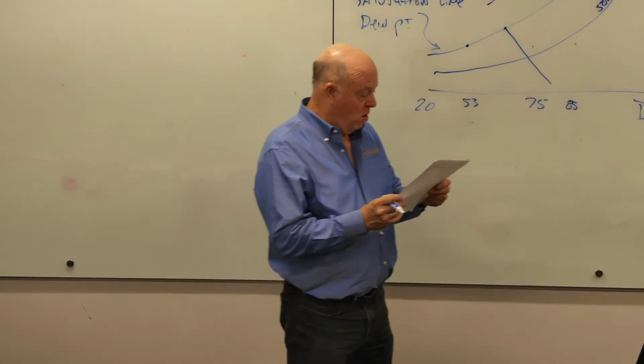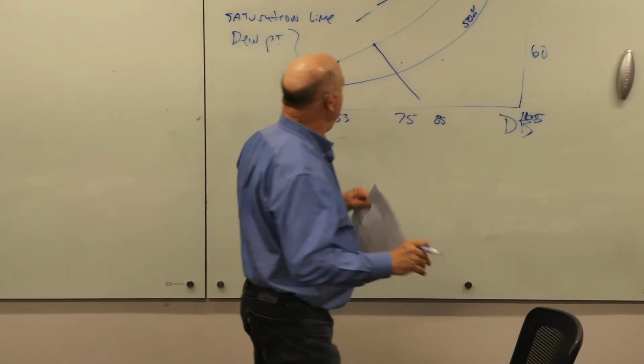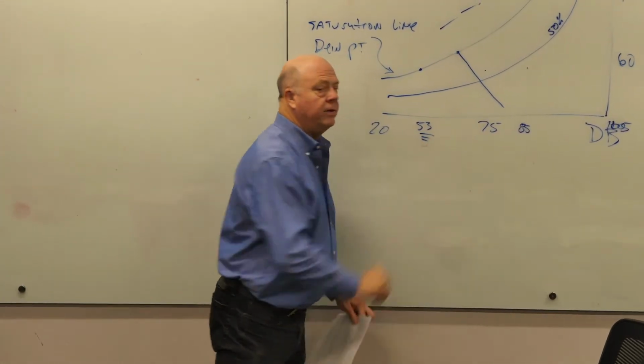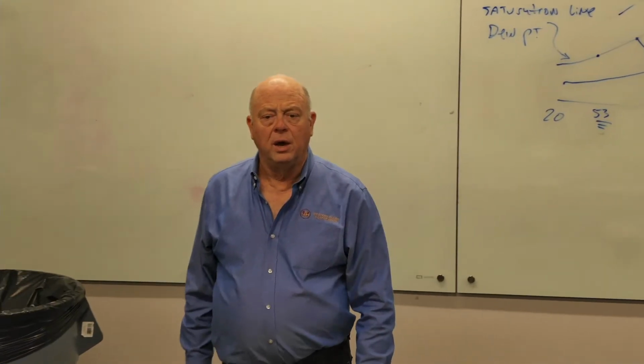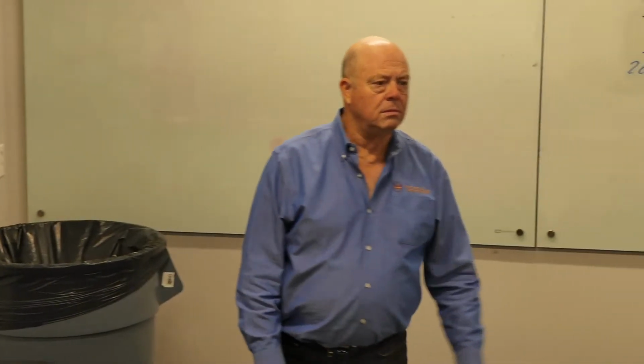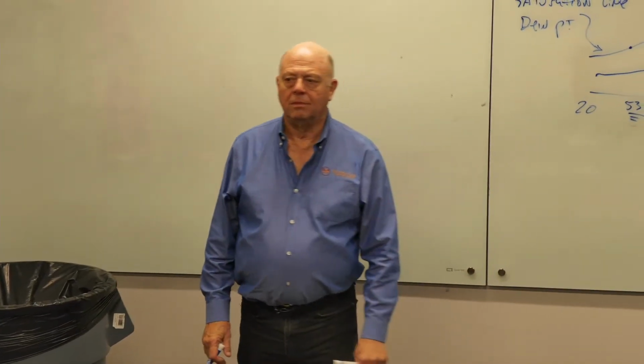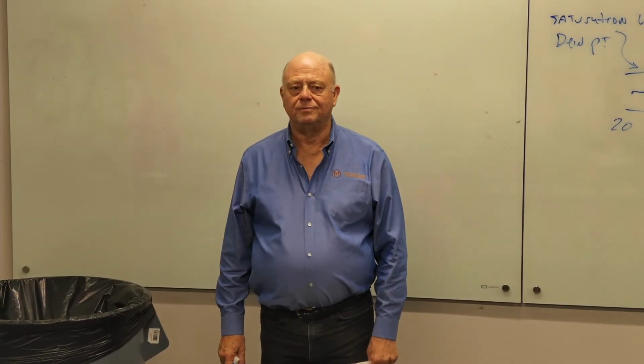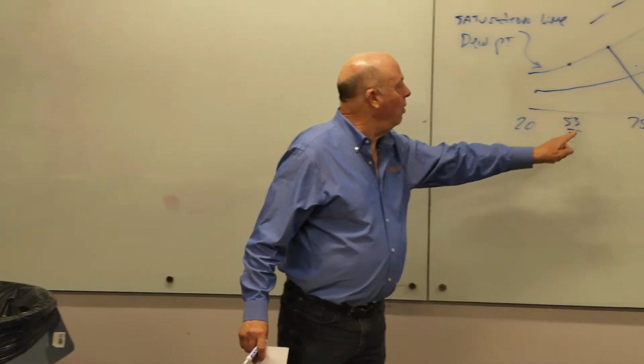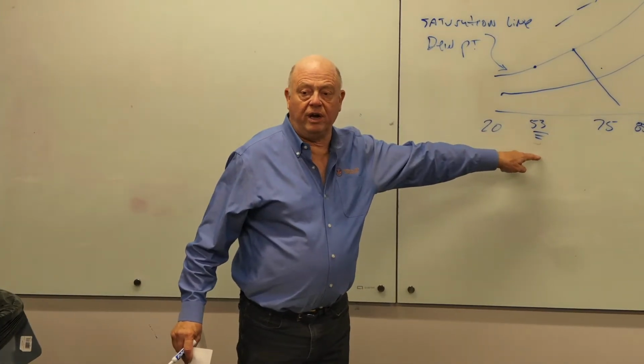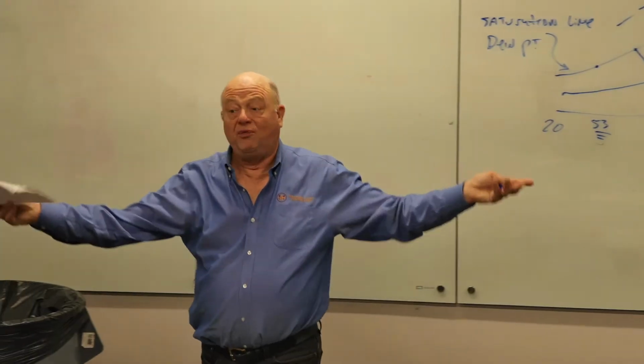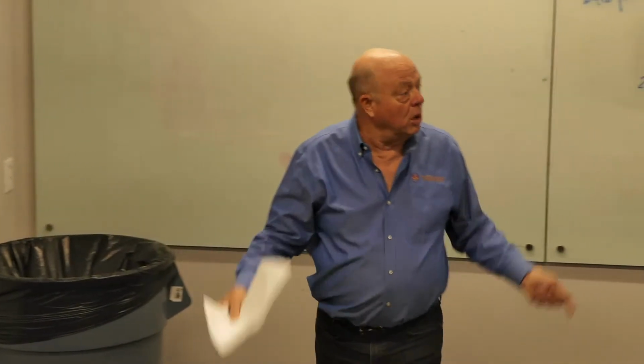Let me ask you a question. If this is the dew point, and we run a duct through here that's not insulated, and it's got 55-degree air in there, will it sweat? Is that hotter than the dew point? Short answer is no. Because if I got a 55-degree duct in a space with a 53-degree dew point, it won't condense. We're above the dew point.